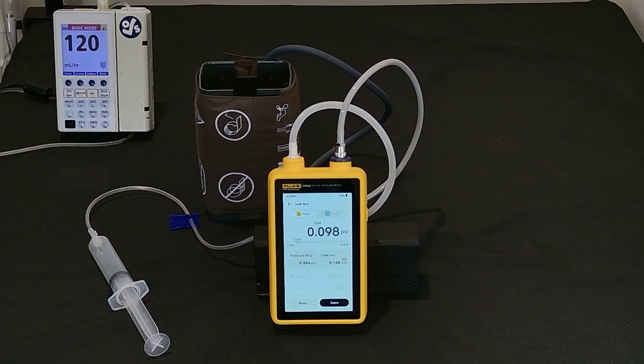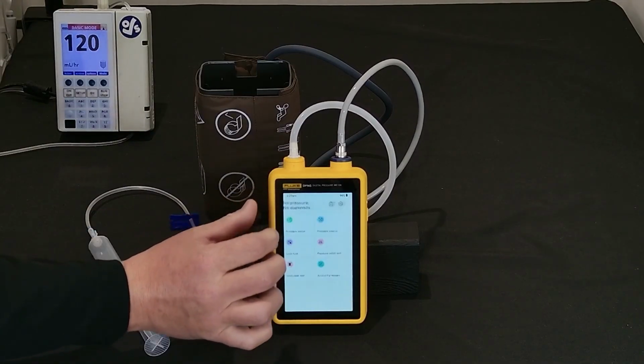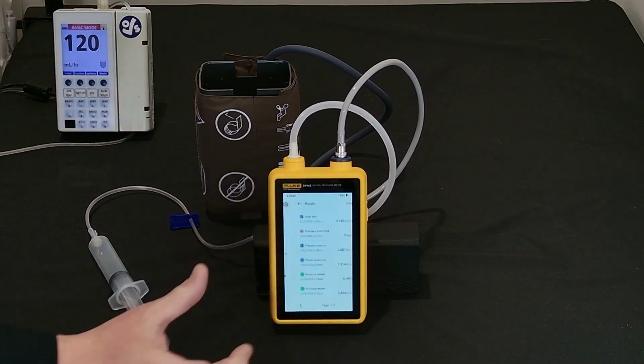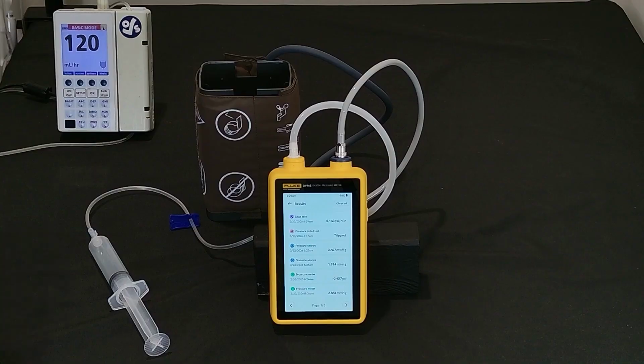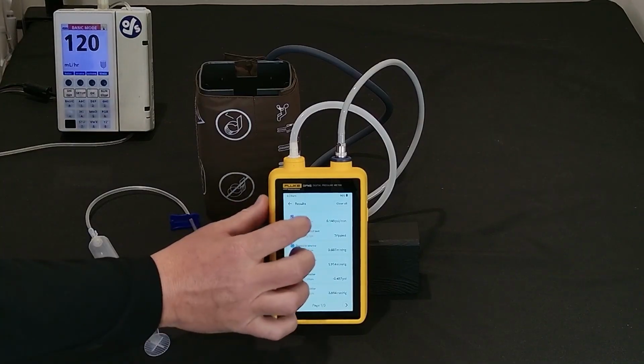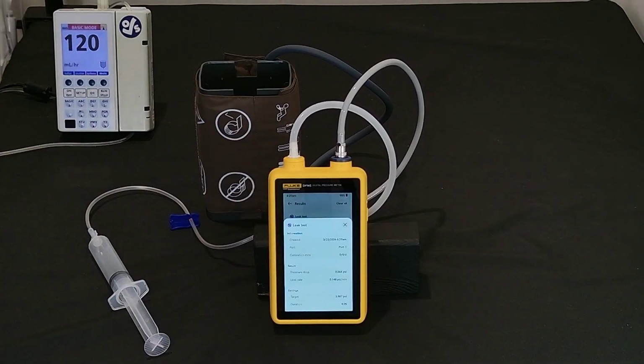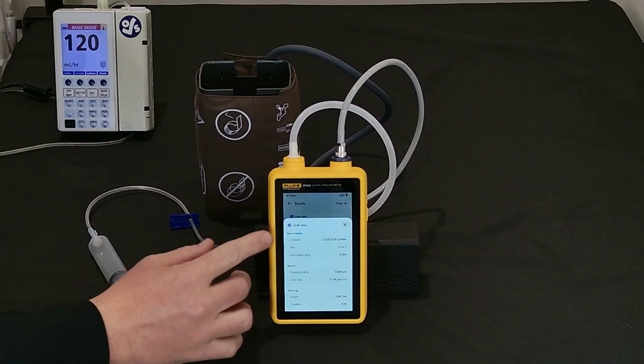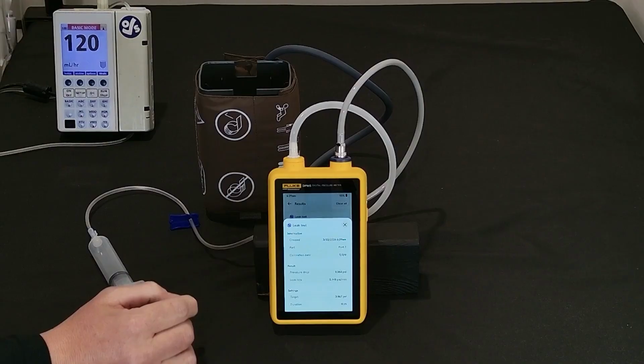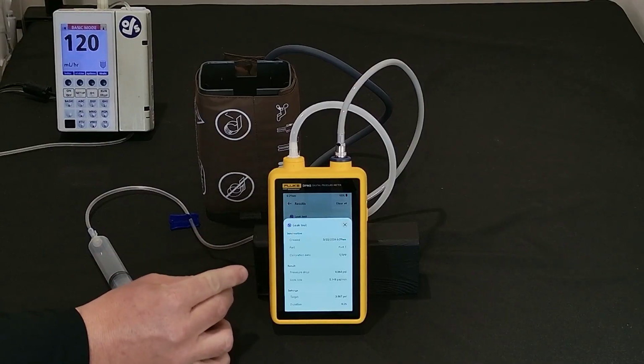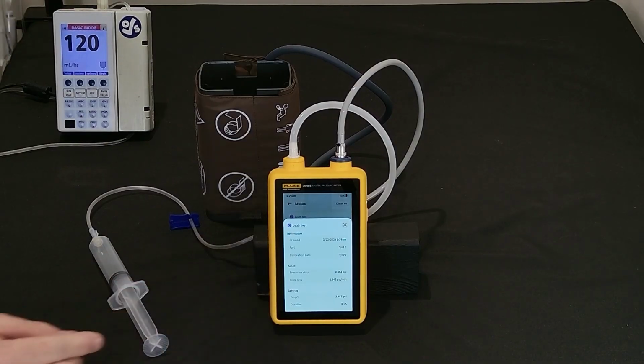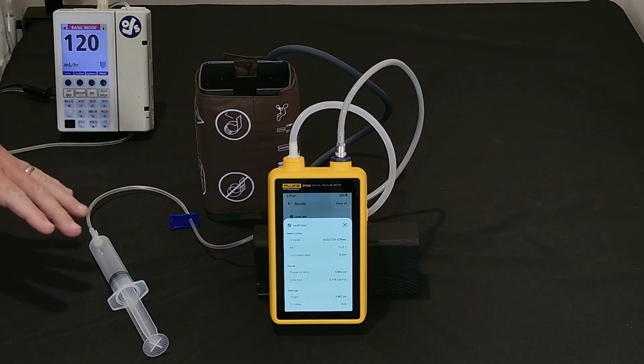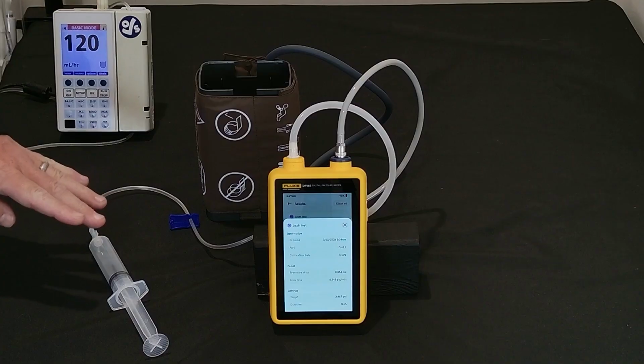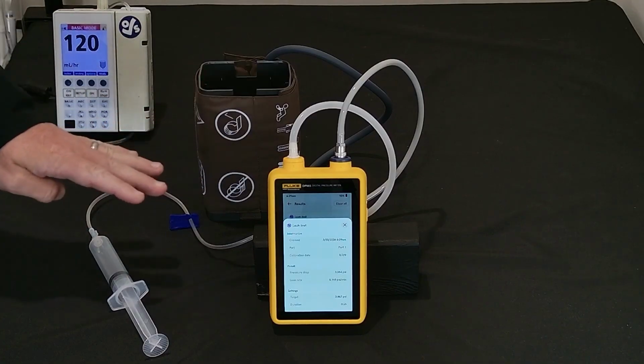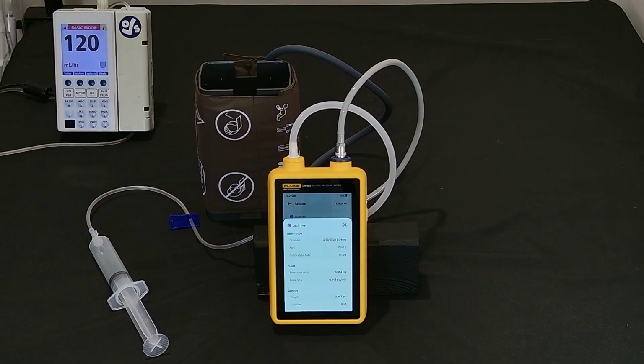Now, all the measurements that we've stored, we can always go back on your clipboard, and there are all your measurements that you've stored. You can see here, it gives you your creation date, what port you used, the test you were running, and all your measurement values. So if you're documenting any of your tests, it's there in your memory bank, or you can export from the DPM.